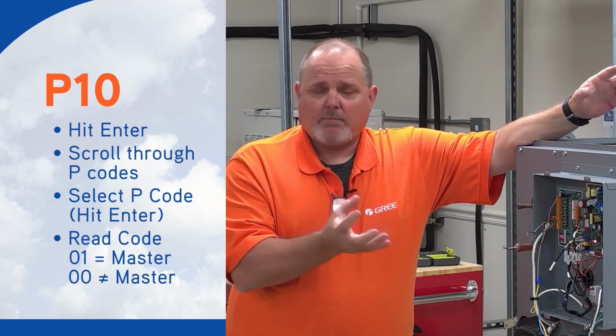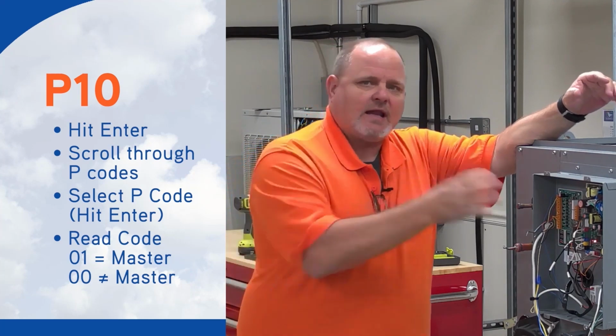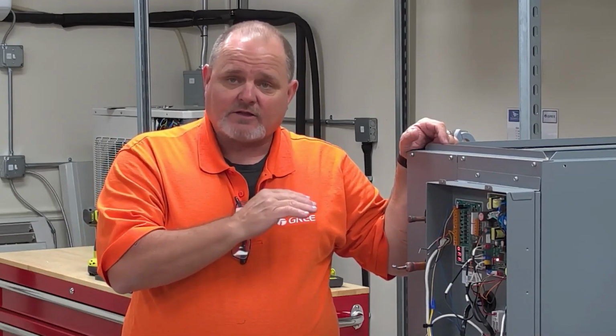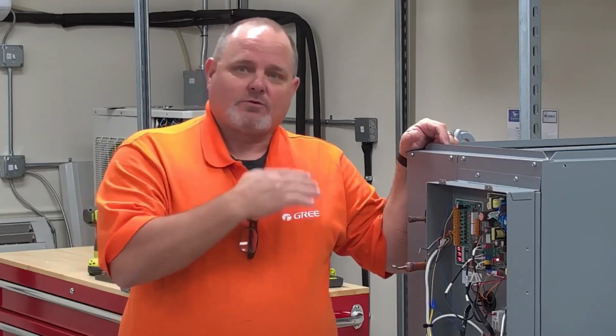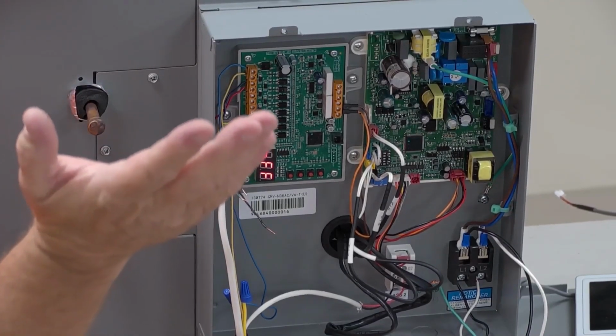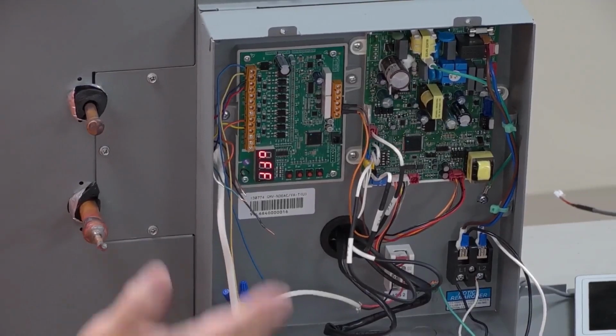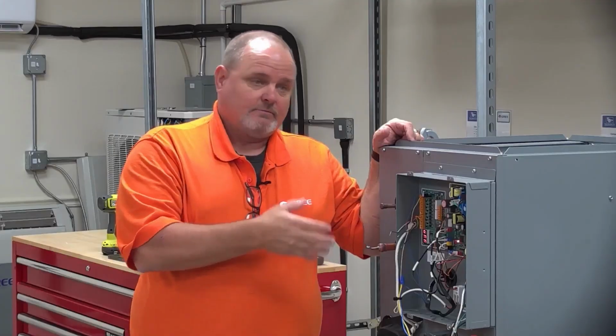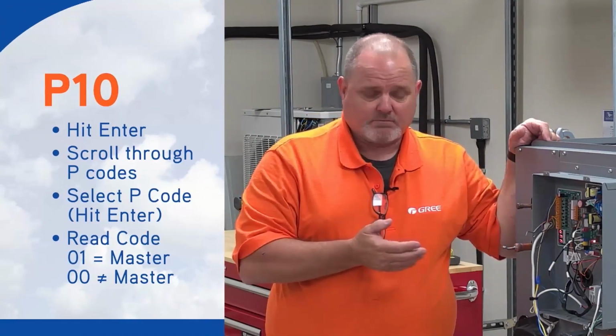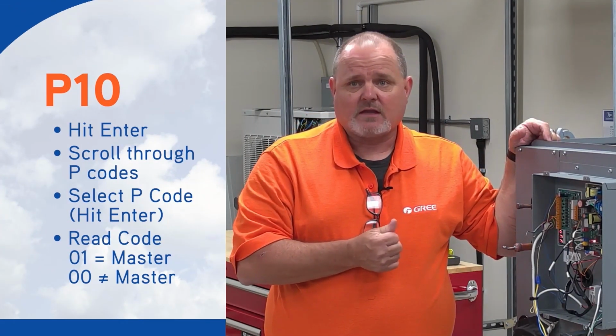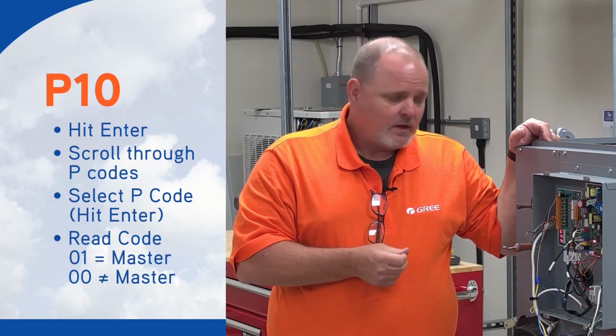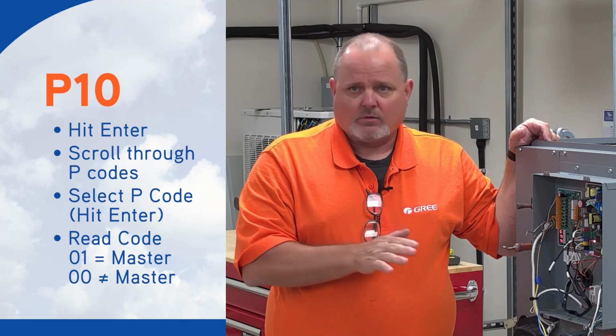The reason why I'm pointing that out is because let's say you're adding this in or you've done some changes or whatever, the MultiPRO system has to have a designated master indoor unit. And the error code you would get is the fact that you have no master indoor unit. So you have to make sure you set one of those pieces of indoors. Now you could have a gas furnace and a high wall, and you can make either one of those the master. I'm just pointing out to you, you have to have one as a master. And if you want this to be the master, P10 is the parameter you need to set so you can get it to become the master, okay? If you don't want it to become the master, leave it 00 and it won't, okay?